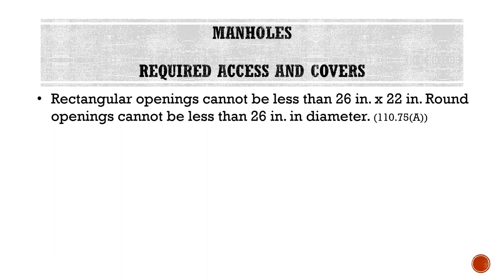Now talking about required access to manholes — specifically the opening dimensions and cover requirements. Rectangular openings cannot be less than 26 inches by 22 inches, and round openings cannot be less than 26 inches in diameter. So depending on which kind of cover it is — rectangular or round — we have some different sizing requirements.